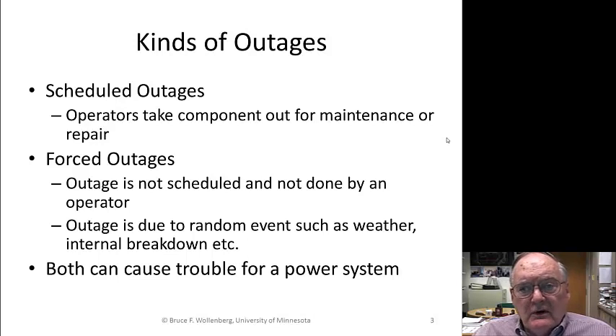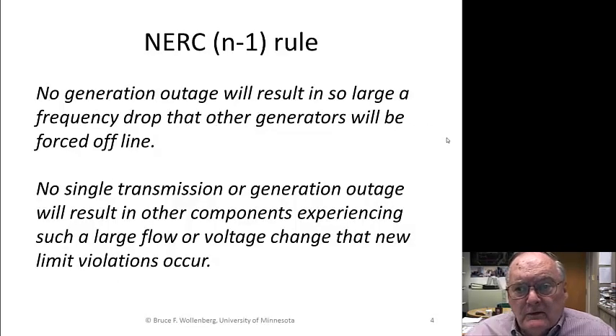Forced outages are those where we have no control over it. It just happens. It's not done by an operator or by a schedule. It's due to a random event such as a lightning strike, an insulator suddenly fails and arcs and explodes, or a transformer suddenly develops a fire and has to be taken out, etc. It can go all the way from small components like an insulator all the way up to big transformers, and to the power plants themselves. The generators can suddenly develop an internal fault, or they can have some other problem and have to go offline. Both forced and scheduled outages cause trouble for the power system.